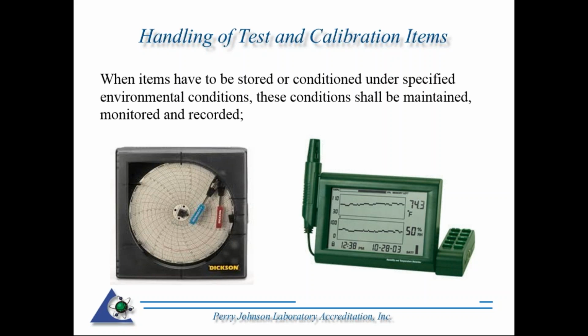On the testing end, I mentioned grain samples that were used to test, in this particular instance, moisture meters. Hence, the moisture content was critical. So if grain samples were kept stored within the facility, there were set parameters as far as the humidity that needed to be maintained. Of course, this is not just during testing. These could pertain to when the artifacts or samples are sitting in your lab waiting to be tested or calibrated, that these particular conditions need to be maintained.